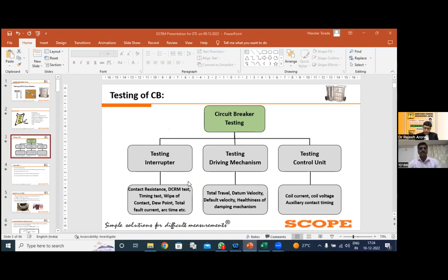So according to this IEC standard 62271-100, the circuit breaker testing is divided into three categories. The first one is the testing of the interrupter, the second one is the testing of the driving mechanism, and the third one is the testing of the control unit. In the testing of the interrupter, the tests we perform on the interrupting contacts, the first one is the contact resistance.